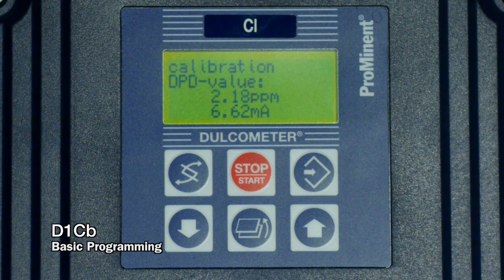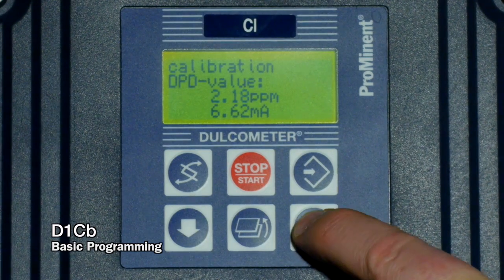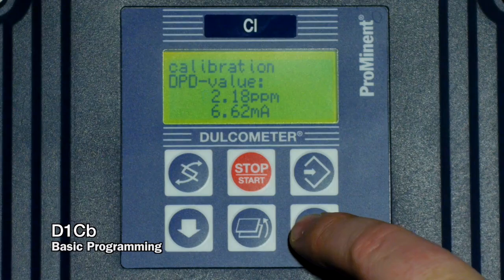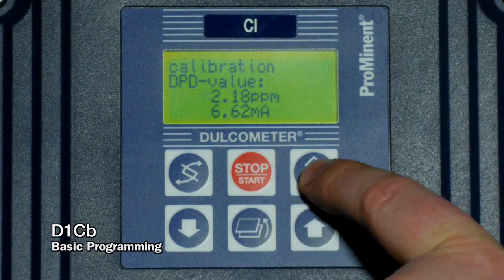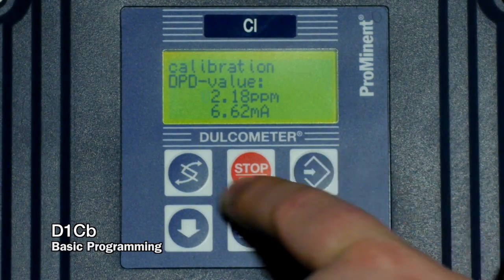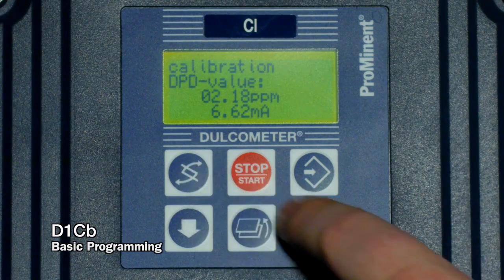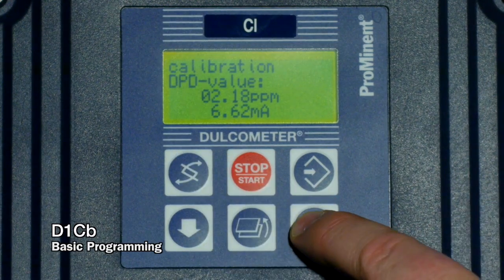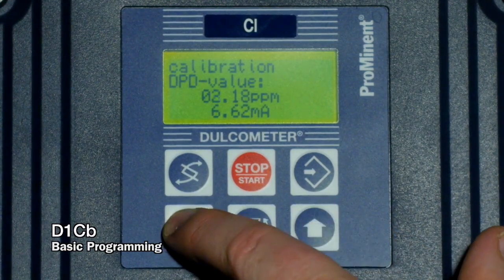So we'll pull our sample and do either a DPD test, or depending on what parameter, you might have to do a titration. But we get to know what that value is of our sample. Now we can make that match with either the up or down arrow keys. Here we change the digit that's flashing. We hit the change key. Now we can change this digit if we needed to.